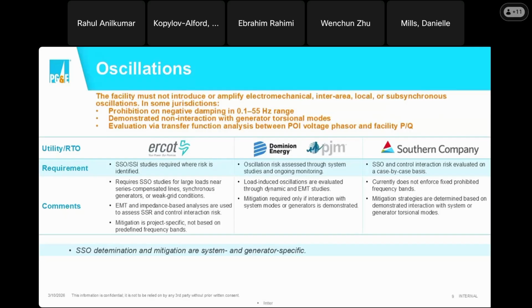A lot of times the feedback is: even within the subsynchronous range, what frequency should we be avoiding? There are different ways these oscillation requirements are being described and discussed, but they are very system-specific and generator-specific, because different generators could have different torsional interaction modes. That's a common theme across the broader system and any other system in the Eastern Interconnect.